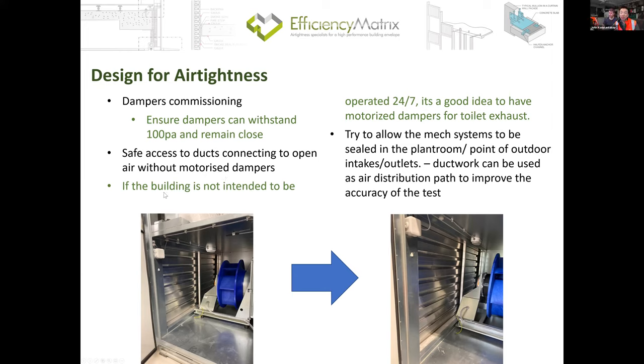And also, if the building is not designed to be operating 24/7, it is a good idea to include a motorized damper on the toilet exhaust to stop unwanted air exchange after hours, to overly pre-cool the building in winter, for example. That's huge. Yep. And then when you're designing the system, try to provide some kind of access panel or some space so we can potentially spray the ductwork inside the plant room instead of needing to jump onto a gondola to seal ductwork on the facade.